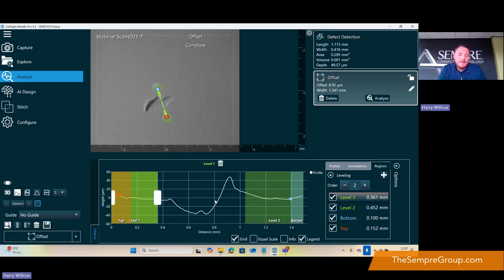Okay. So this is a good point to touch on the accuracy differences between the Series 2 and the Modulus. The Series 2 system is qualified between 1 and 50 microns at 1 micron plus 4% of the expected depth. So if we were looking at a defect that was 10 microns deep, we would be at 1.4 microns of accuracy. Now there's a slight difference with the modular system in the classification of the accuracy. As opposed to it being between 1 and 50 microns, we start the accuracy statement between 5 and 50 microns. And the accuracy statement of those levels is the same as the Series 2. So effectively, when we're looking to quantify the sort of couple of micron defects, the Modulus is probably not best fit for those defects currently. So we'd be looking between 5 and 50 microns. We are 1 micron plus 4%.